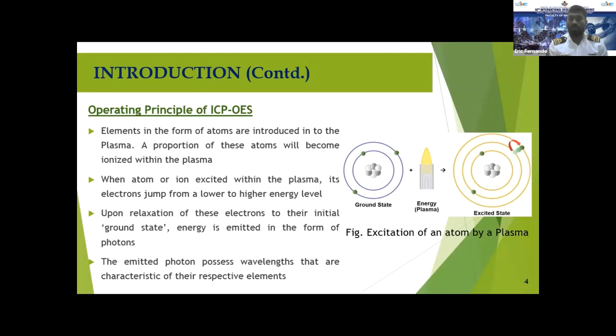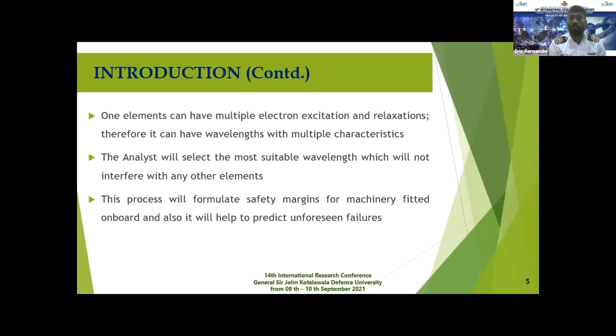These emitted photons possess wavelengths that are characteristic of their respective elements. But one element can have multiple electron excitations and relaxations, so it may have various characteristic wavelengths. It is the duty of the analyst to select the most suitable wavelength, one which will not interfere with any of the elements we are going to test in our oil samples. This process will finally formulate safety margins for the machinery fitted on board, and it will also help us predict unforeseen failures.